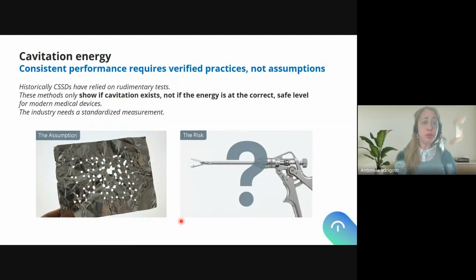So consistent performance requires verified practices, not assumptions. Historically, CSSDs have relied on rudimentary tests. These methods only show if cavitation exists, not if the energy is at the correct, safe level for modern medical devices. The industry needs a standardized measurement. Okay?